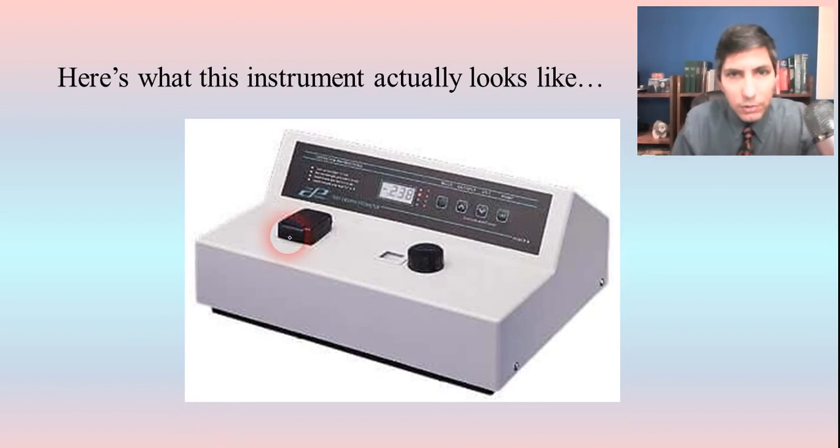Now, this is what the thing actually looks like. The little slot here, there's a little door here. And you will slide the cuvette in there that has the solution in it. And there's a dial here where you're able to adjust the wavelength. You can change the color that's being allowed to pass through. And then, the light detector is in there. And it's attached to this electronic readout. So, there's an actual readout there. In this case, it's a digital readout that tells us the absorbance.